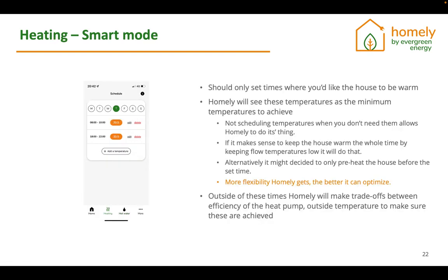Now, heating mode is the bit that is really important in smart mode and standard mode to be explained to the customer. In smart mode, this is your heating in that perfect weather compensation world. So what the customer actually sets up when they are selecting their set points is the minimum temperatures that they would like to be maintained at specific times of the day. And in this case, it would be 20.5 degrees in the morning, 20.5 degrees in the evening. The customer should only set the times that they need these minimum temperatures so that Homely can have the flexibility around these set points to actually make the right decisions for them.